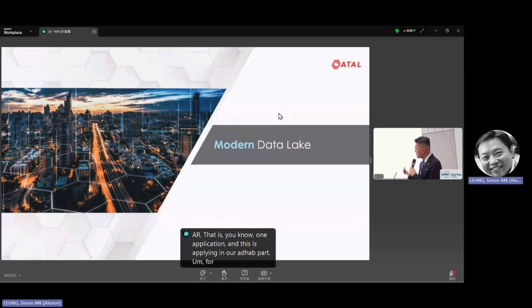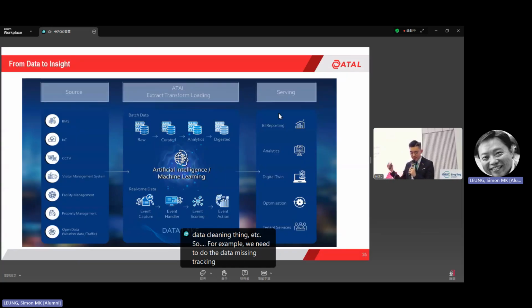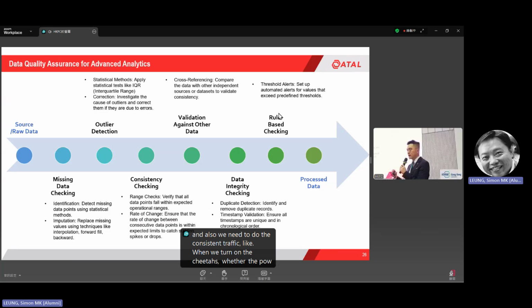For the modern approach, as I said, using BACnet, we obtain the raw data. But of course, data needs to be processed, like doing data cleansing, etc. For example, we need to do missing data tracking, whether there's any missing data or any data outlier, and also we need to do consistency tracking, like when we turn on the chillers, whether the power goes up as well. If the data is not consistent, then there's something wrong with the measurements.